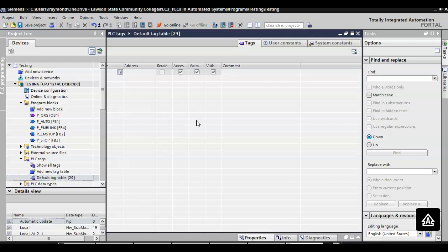This is the big problem, and this is what PLCs don't do anymore. They don't assign all this memory inside your PLC. What they do is let you assign it. In RSLogix 500, that status register is already inside there, whether you use those timing bits, first scan, or any of that stuff. They sacrifice that memory in RSLogix 500 to give you access to those features. Your new PLCs don't do that. If you want those timing bits, you've got to enable them. If you want first scan, you've got to enable it. And that kind of stuff is hard to find.